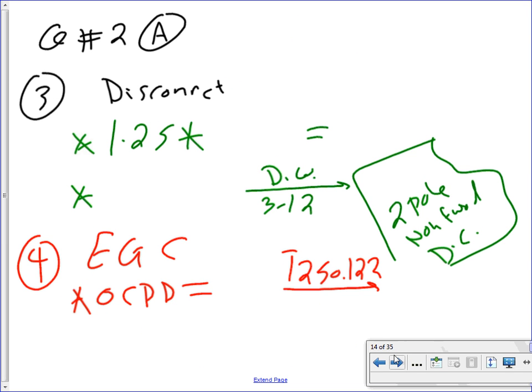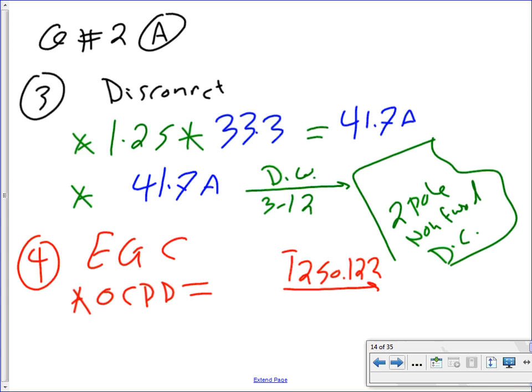Disconnect. For the disconnect, my friends, I use 1.25 to size my disconnect. 1.25, assuming it's a continuous load, here is my 33.3. That will give you 41.7 amps, and you take your 41.7 amps, that will get you a 60 amp 2-pole non-fused disconnect. That 1.25 for the disconnect is from the code. We're assuming it's a continuous load and we're sizing our disconnect at 1.25. Would I ever use 1.15? Probably you would. But I size it like a conductor.